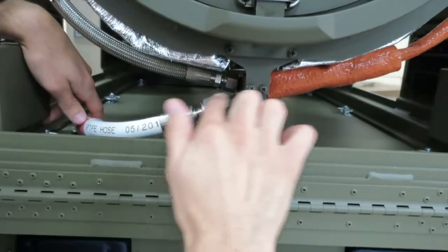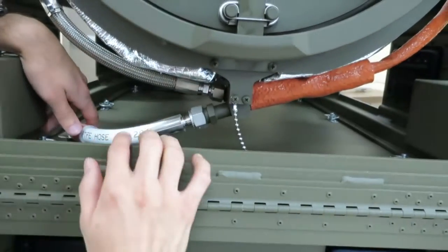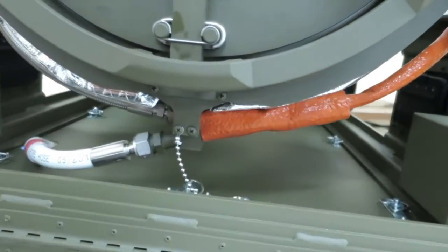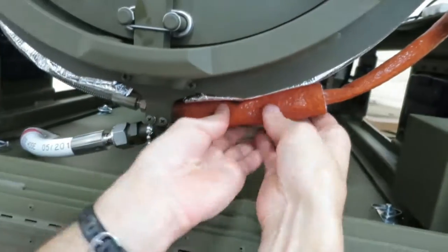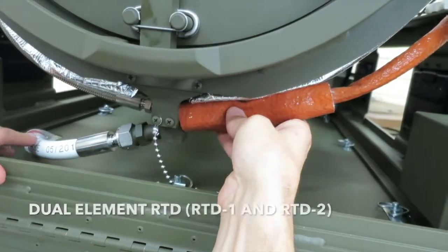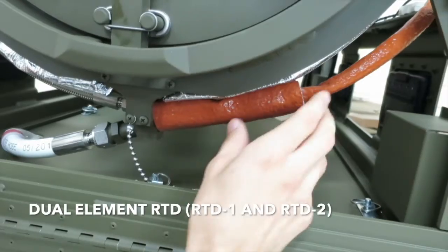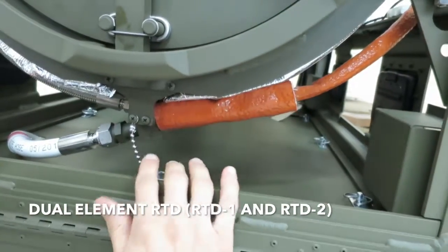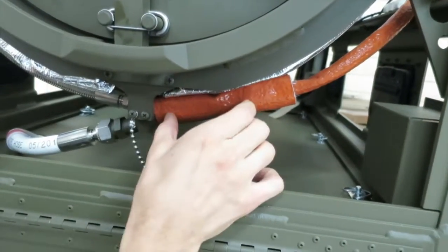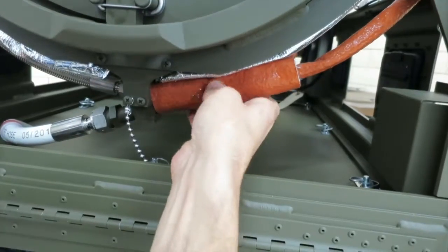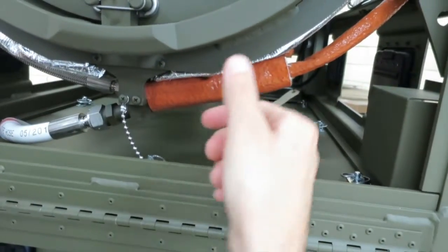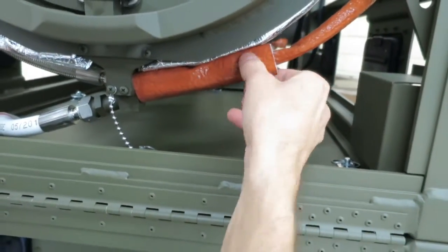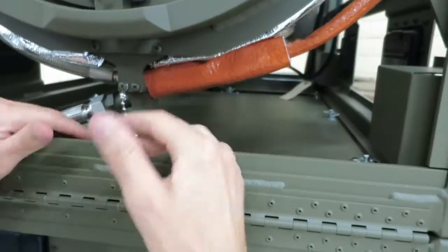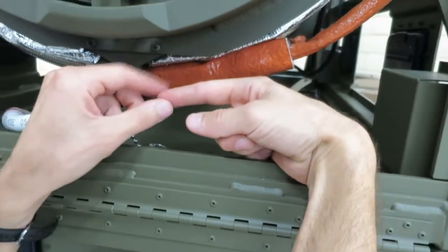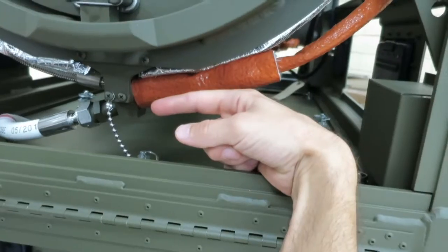That's why we have that angle there, so the condensation will drip down with gravity. Finally, we have the RTD probe. If I were to slide this insulation out of the way, I would see some 1/2-inch Swagelok tubing there. And if I were to remove the nut right here, I could pull out the probe. The probe has two elements in the end.